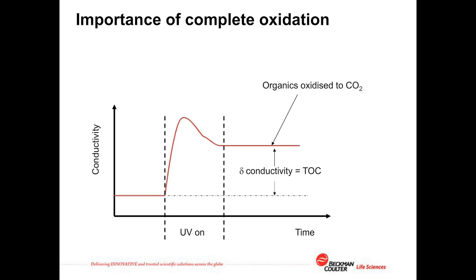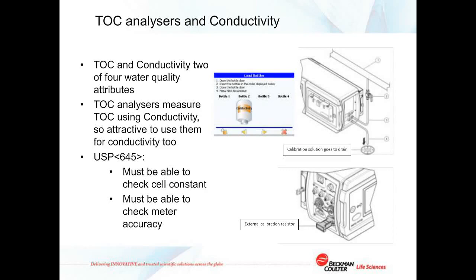The problem is that as complex long-chain molecules are broken down during the oxidation process, they may form organic acids, which contribute more strongly to the water conductivity than the final carbon dioxide does. If the TOC analyzer does not complete the oxidation of the organic molecule, one of two things may happen. Either the carbon remains bound up in the organic and cannot be measured, so the TOC is actually underreported, or the TOC analyzer takes a conductivity measurement before complete oxidation when the organic acid is present and overreports the amount of TOC in the water. Either way, assuring complete oxidation is the only way to measure TOC accurately.